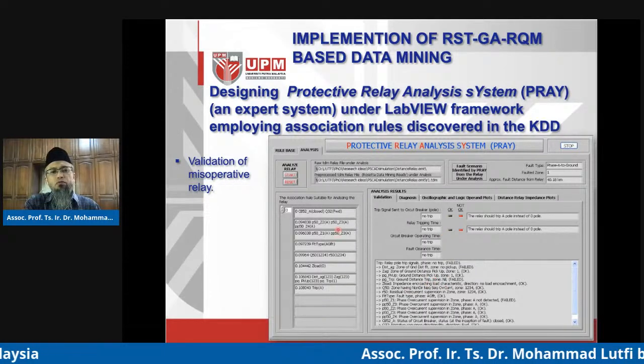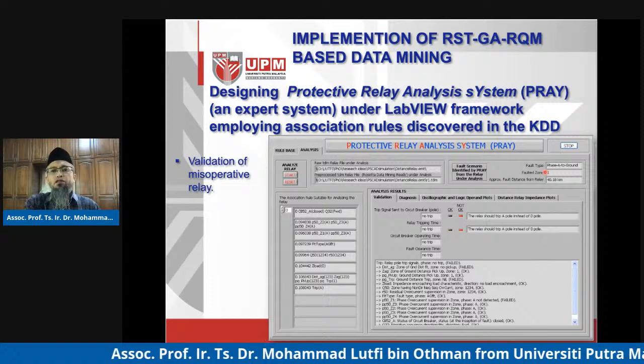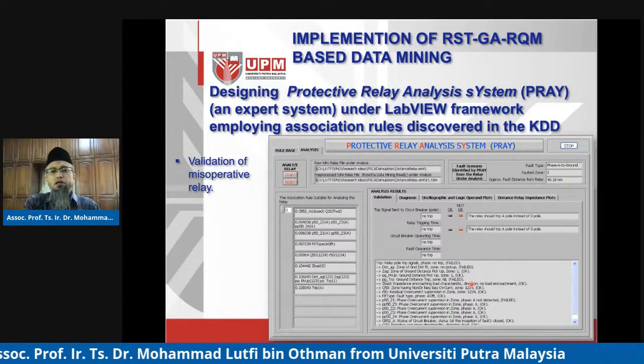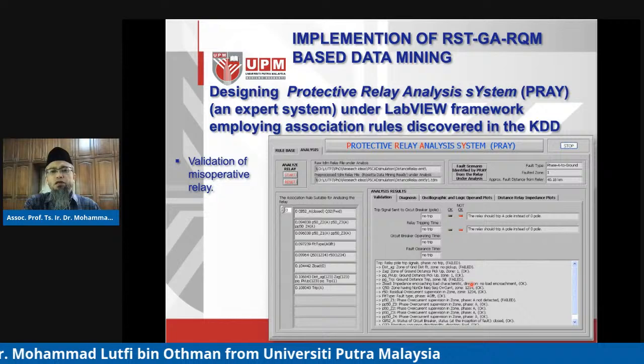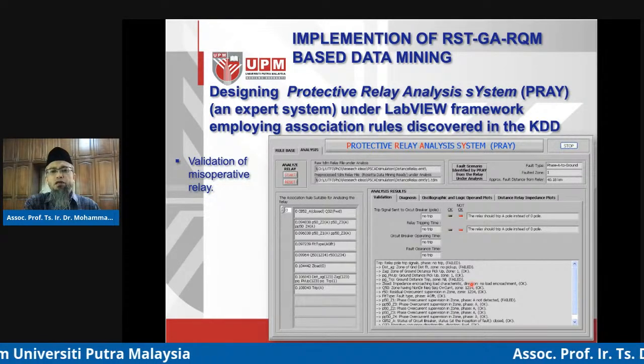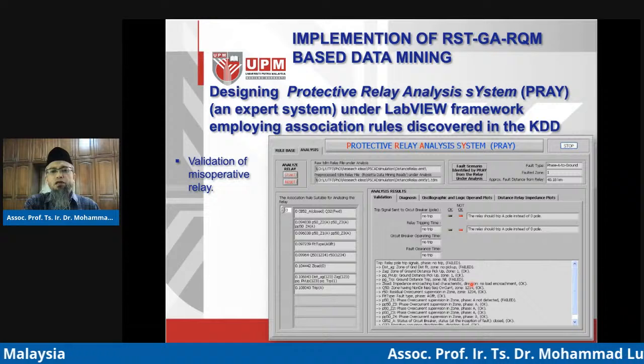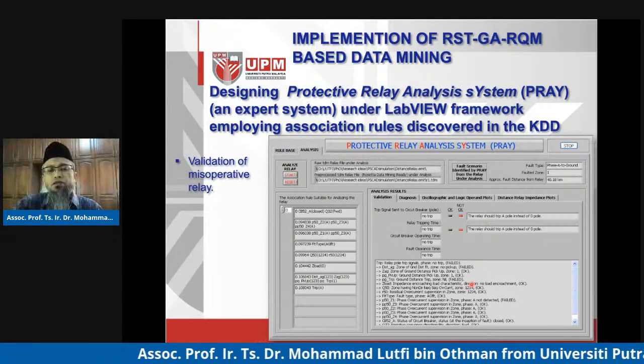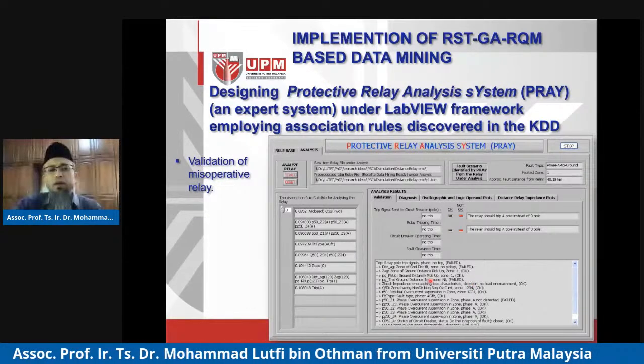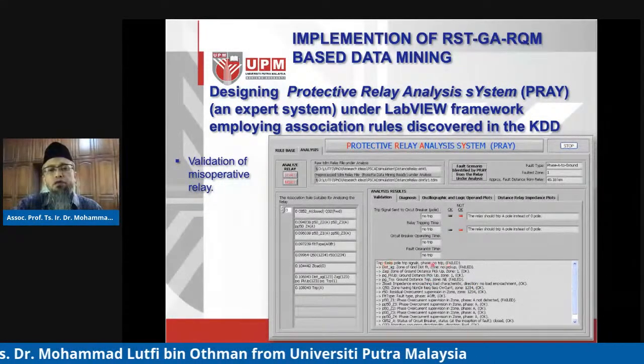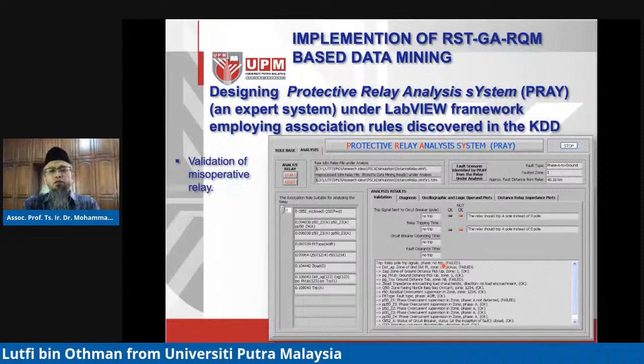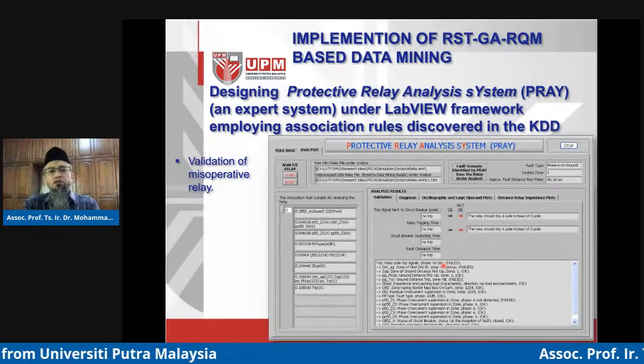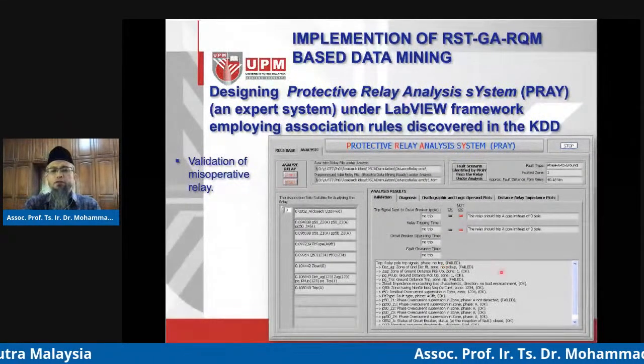And if you were to compare the rules with the event report or the data that's resident in the relay, this ground distance relay has failed to operate. And finally, at the top level, we see that the tripping signal has not been able to be given out to the circuit breaker to actually trip the circuit breaker.